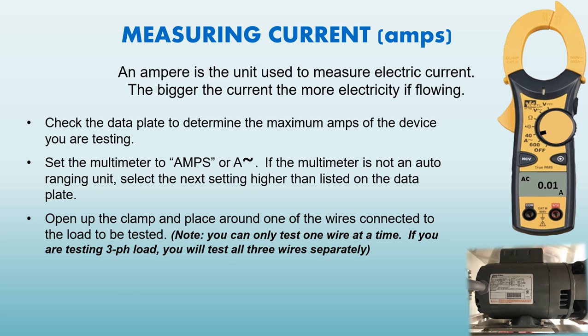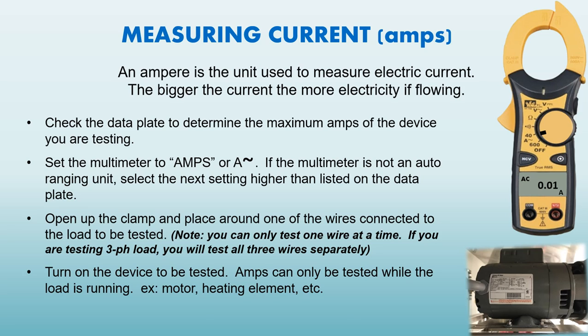Set the multimeter to amps, or the A with the sideways squiggly line. If the multimeter is not an auto ranging unit, select the next setting higher than listed on the data plate. Open up the clamp and place it around one of the wires connected to the load to be tested. Take note, you can only test one wire at a time. If you are testing a three-phase load, you will test all three wires separately. All three wires should be no greater than the amperage displayed on the data plate.